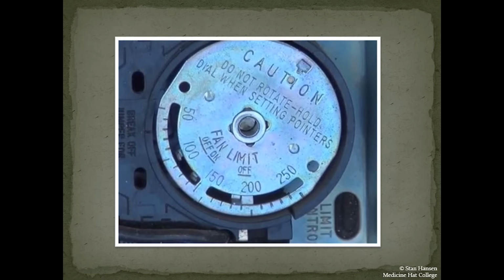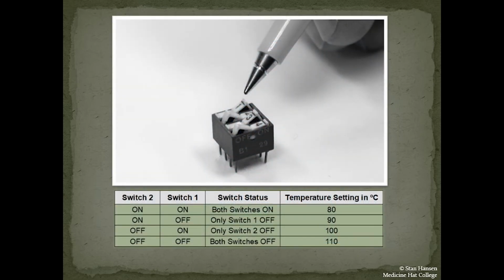If you use a disc type high limit, they are not adjustable, so they need to be preset anywhere between 80 degrees Celsius and 120 degrees Celsius. For our spiral type, like you see on the screen, that should also be set within this range. The newer models of furnaces use thermistors and electronic circuit boards to regulate the high limit control. These are much more reliable and they're programmed using dip switches. The switch orientation itself will determine what the temperature maximums are going to be. And the more dip switches that we have, the more available settings we have as well.